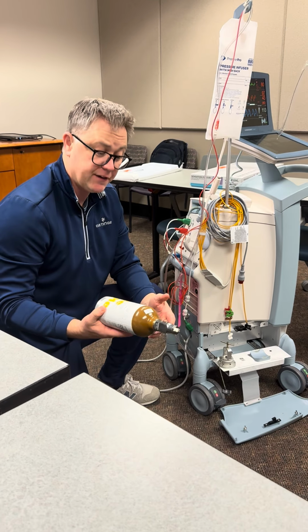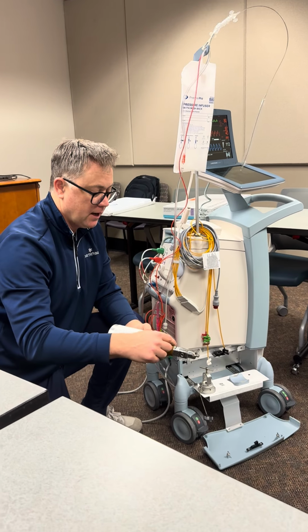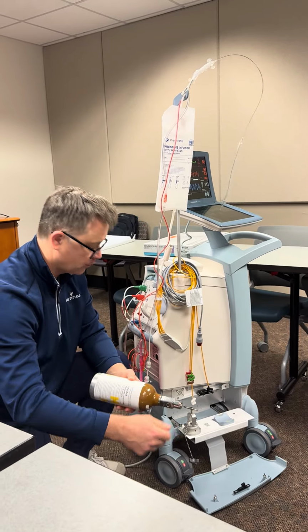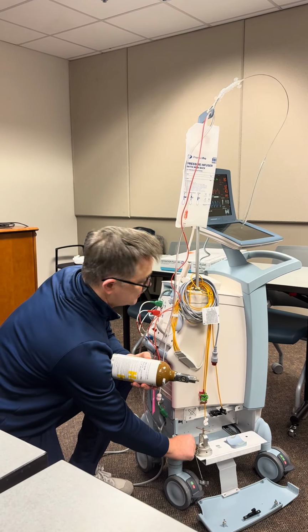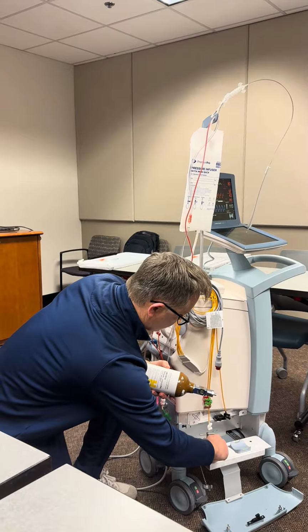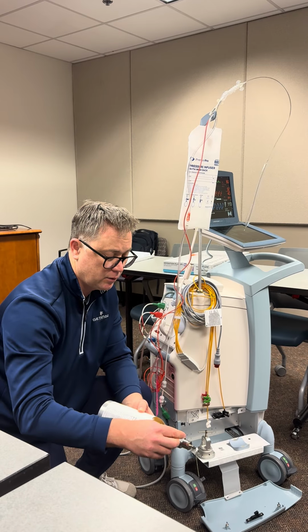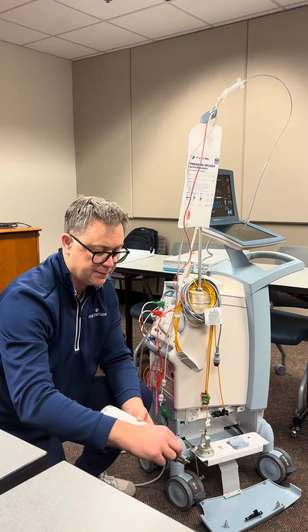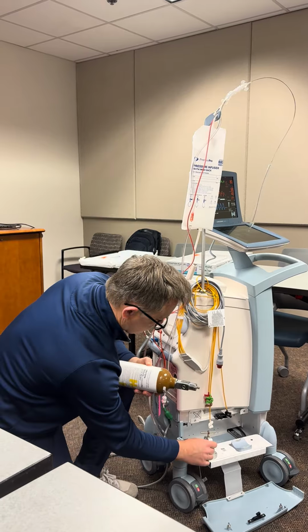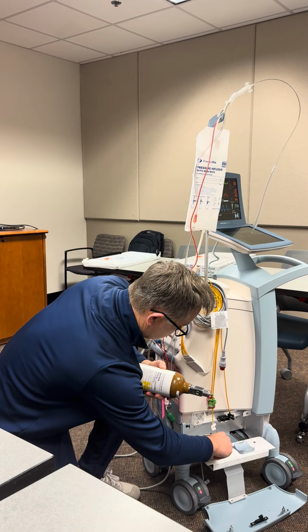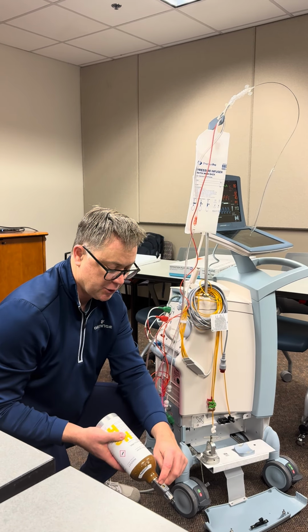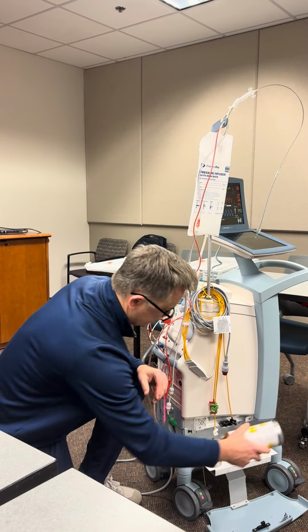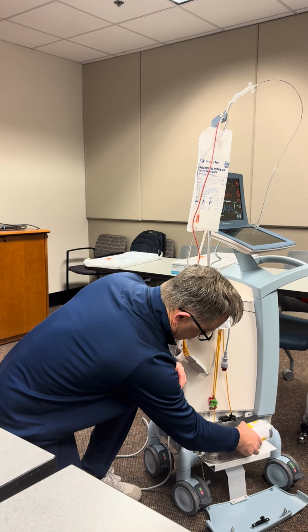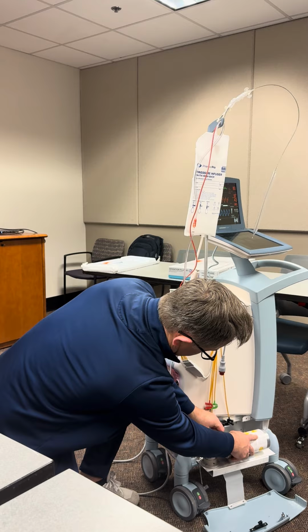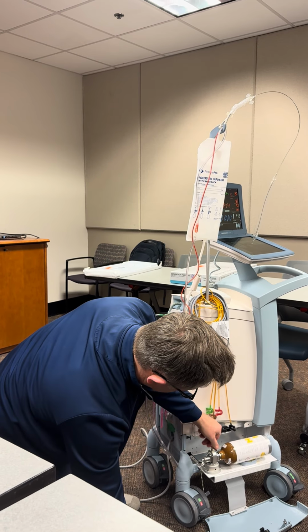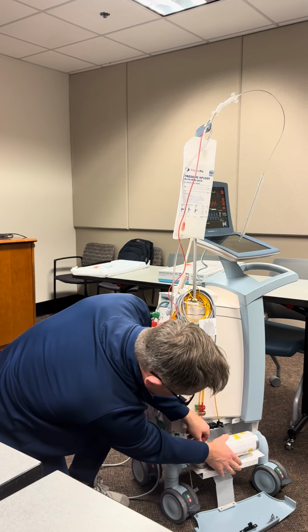The new tank, these are refillable, so keep those, give them to your biomed guys. The new tank's going to come with a little plastic strip and a rubber O-ring. You actually have a spindle here with extras, and then there's a little seal, a little rubber O-ring that needs to be changed. So the new one will come with a little rubber O-ring on top here. You pop that plastic band, grab your new rubber O-ring, and slide it in here. This is just a seal. Goes in like so. And then you've got to line up the two little dots here when you take your new tank and slide it back in, lock it in there, lock it down.